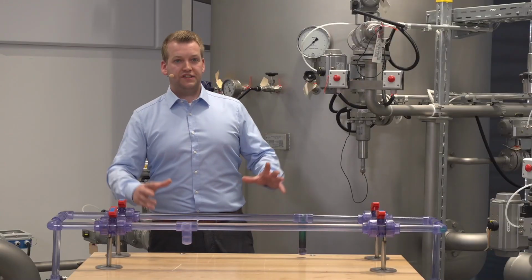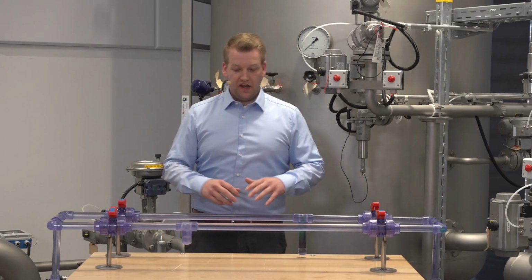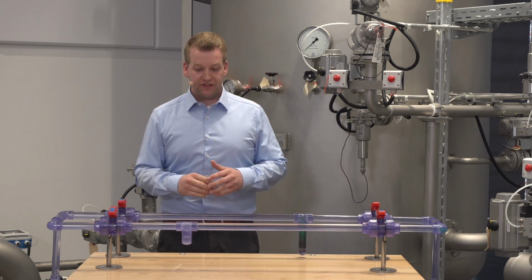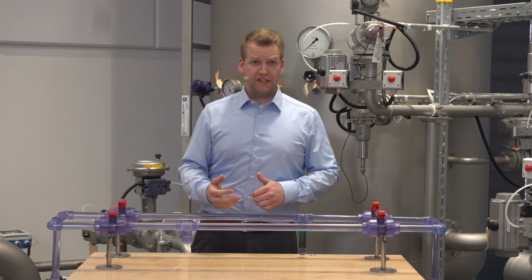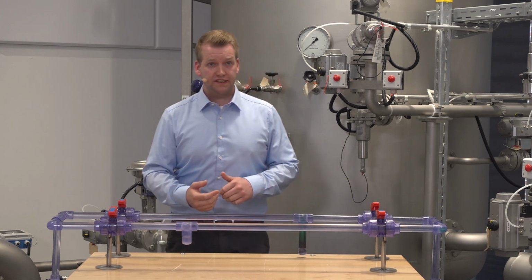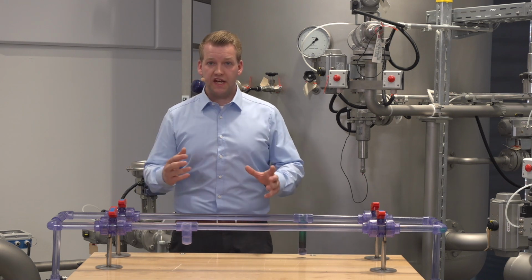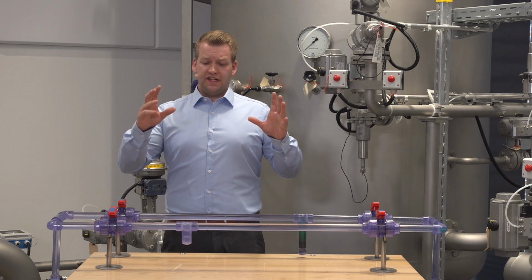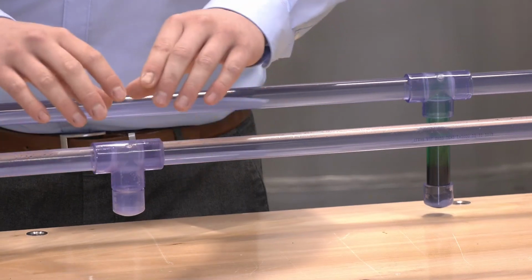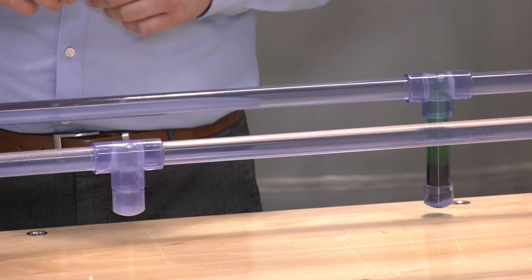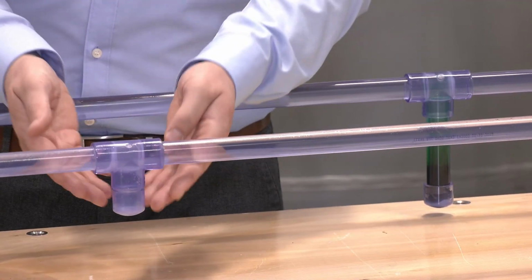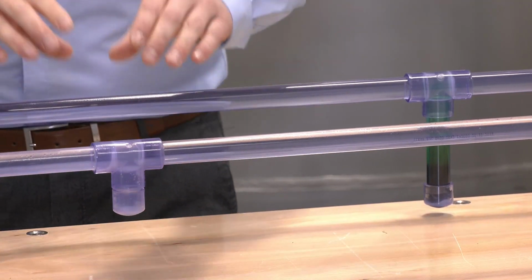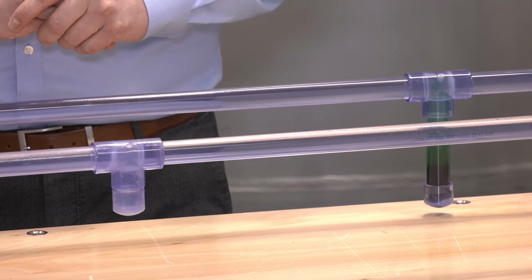So this was the second demonstration, and if we now compare the colors, this is typical for your cleaning process. We are talking about the SIP process and the CIP process. I told you before what this process means. At 1.5 we have a very good cleaning result. You see the dirt is flushed away, so we see efficient cleaning of this pipeline.